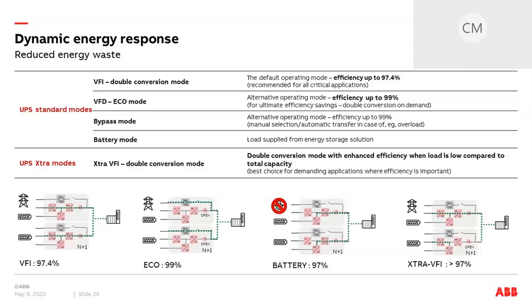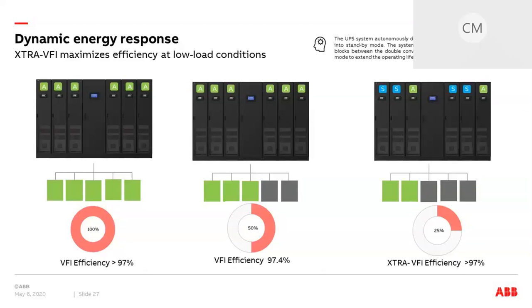But if you have a reliable grid supply on site, the machine can run in eco mode, having up to 99% efficiency. And in the other case, when the power sources are not available, the system is able to run in battery mode together with the energy storage solutions. And if the load conditions are going low, then the xtra VFI mode can be activated to deliver improved efficiency for the machine. But the question here is how we maximize the efficiency at low load conditions. This is thanks to the xtra VFI operating mode, which optimizes the efficiency for low power demands.